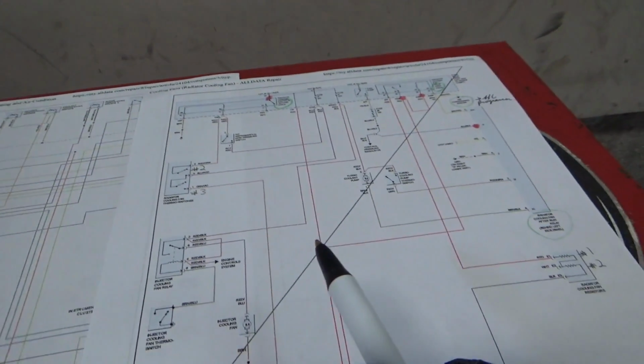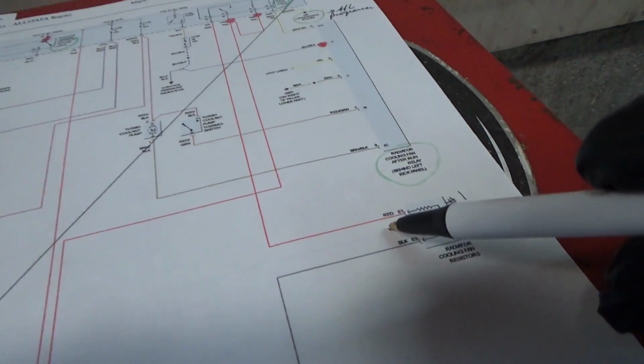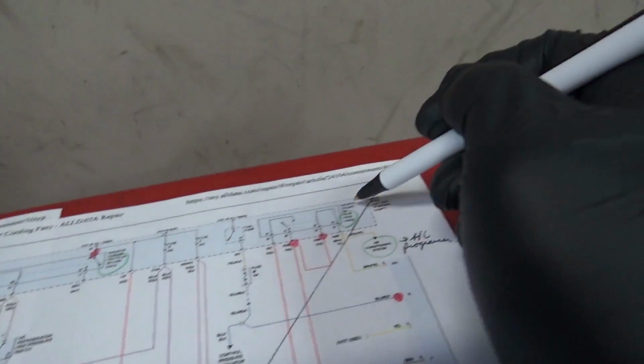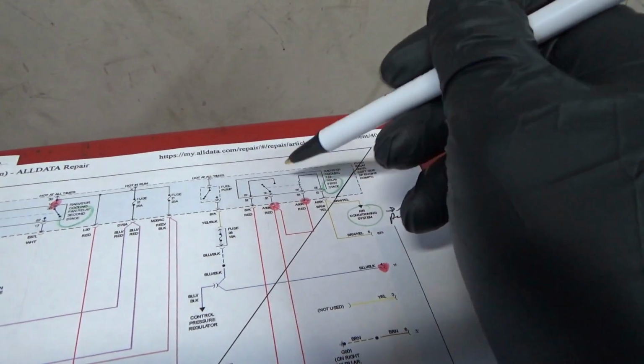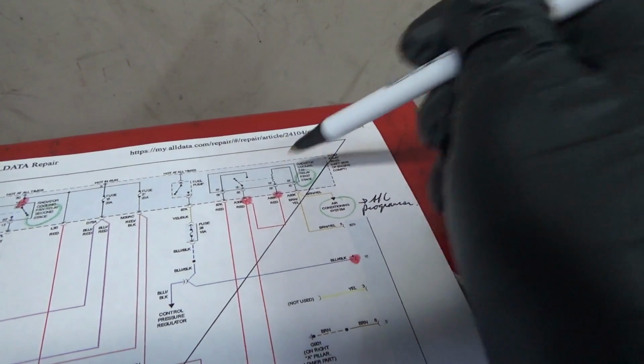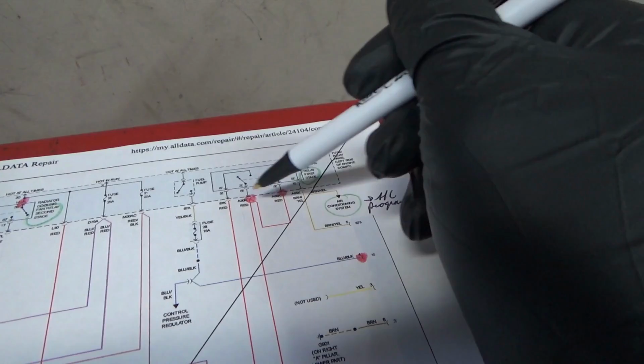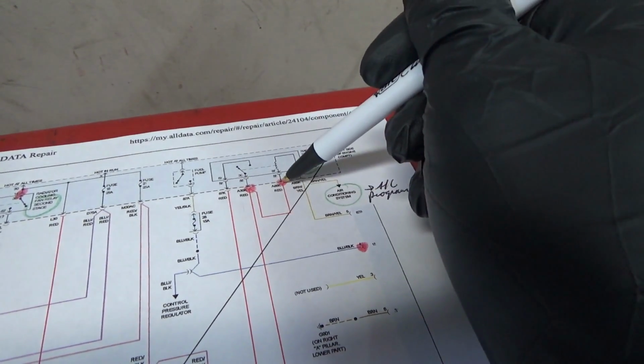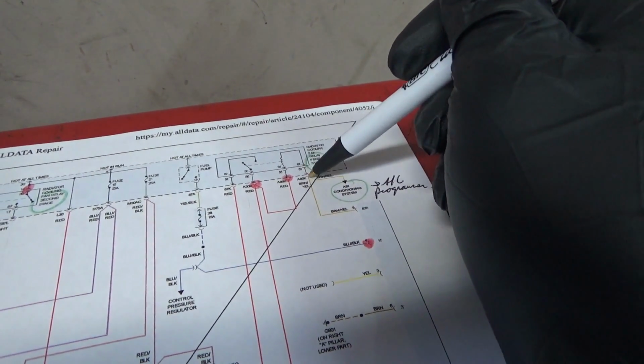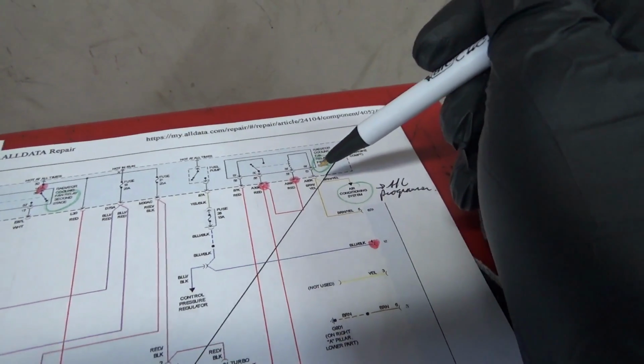Finally, for low speed fan operation, from this resistor comes the 1st stage relay. And what triggers that relay to kick on? Well, let's see here. The control side, we have constant power on one side, so whenever this pin is grounded, you would get low speed fan.